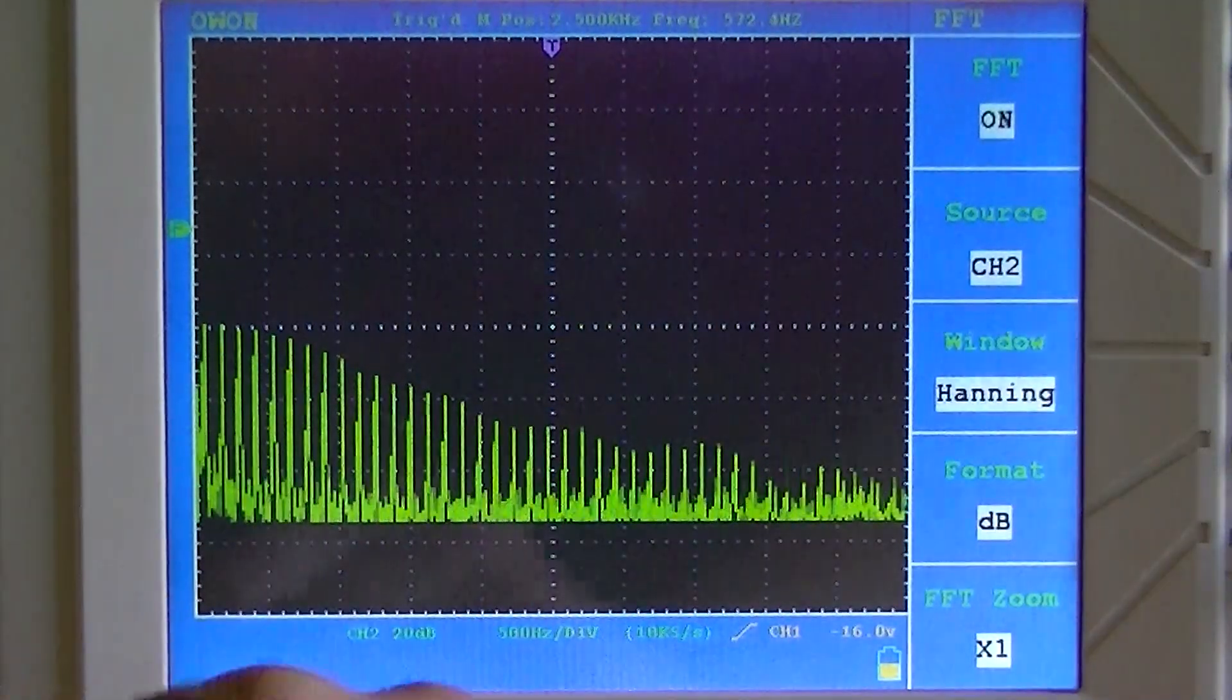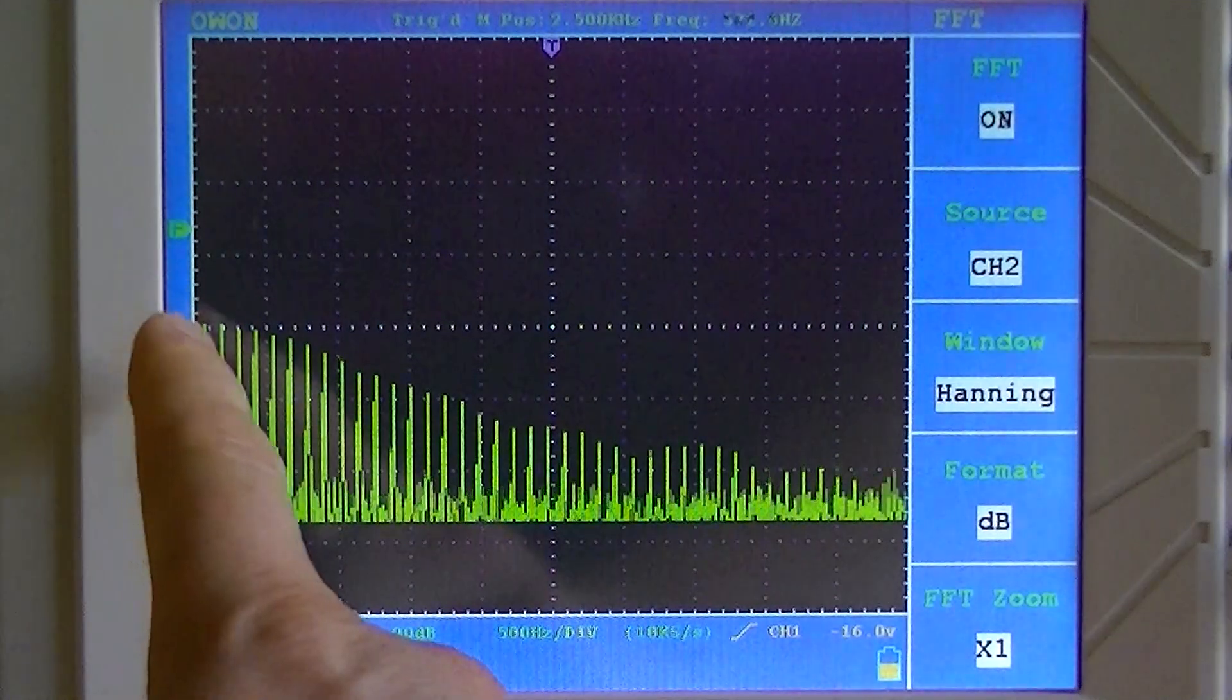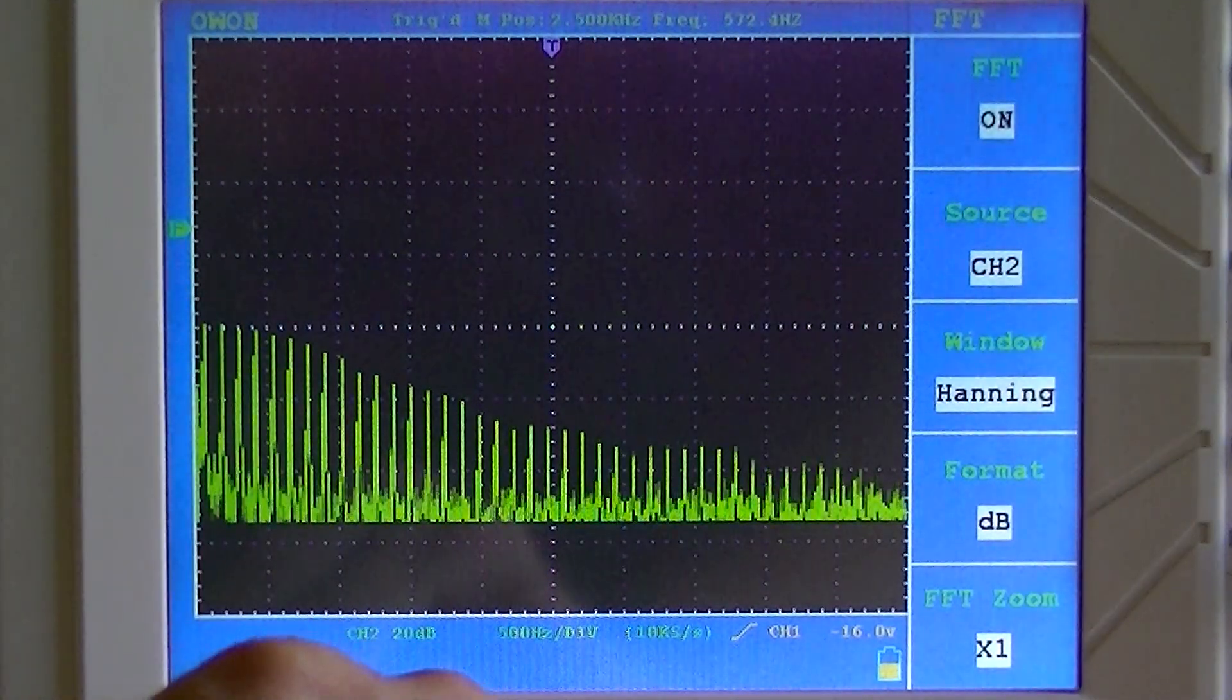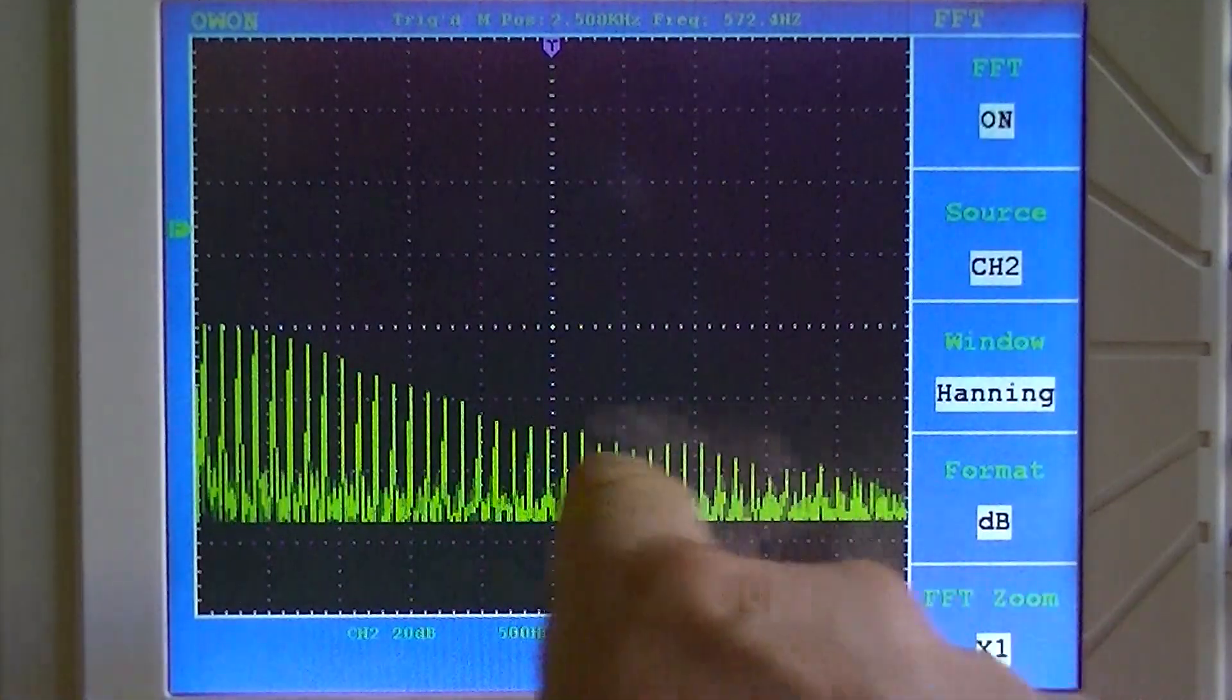And all these spikes are what are known as the harmonics. So if we were taking a pure sine wave off the system, we would only have the first spike, which would be the fundamental frequency, and all these other spikes wouldn't be present.